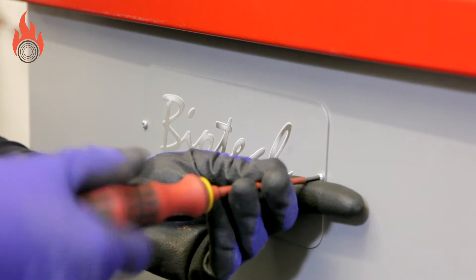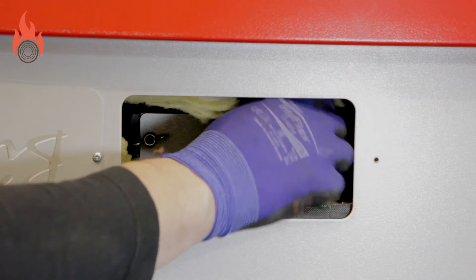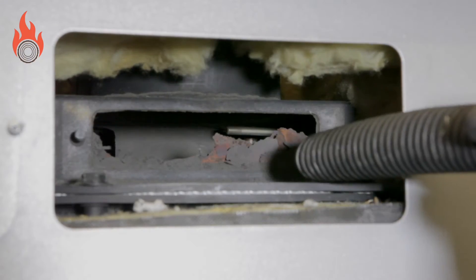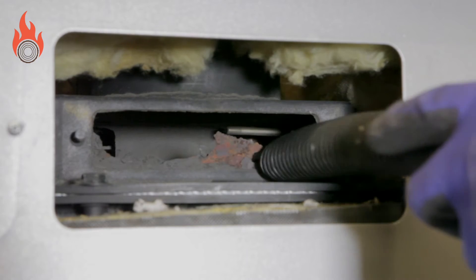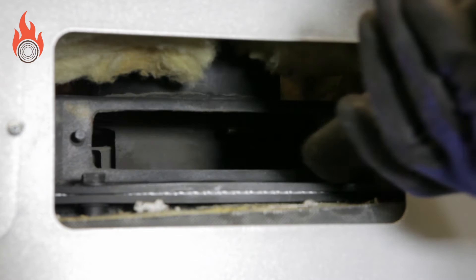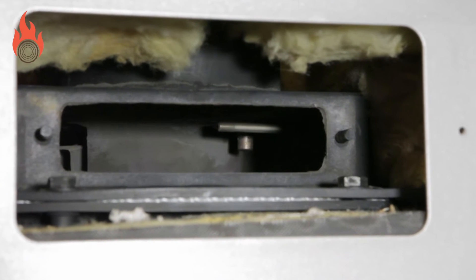The flue gas outlet is cleaned via the inspection plate known as the letter box. Remove the inspection plate of the induced draft fan and remove any deposits using a vacuum cleaner. Also check that there is no debris around the lambda sensor, which should be visible through this inspection plate.